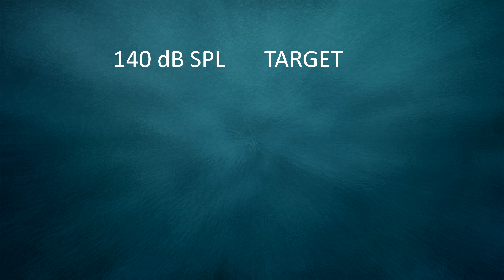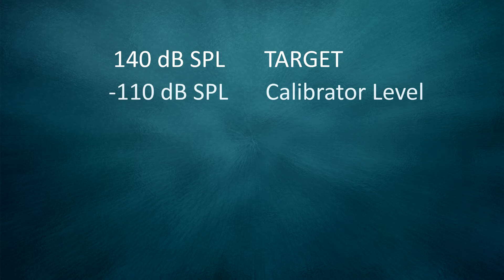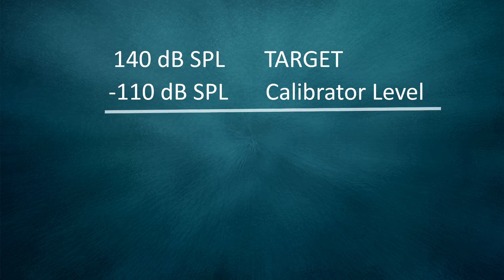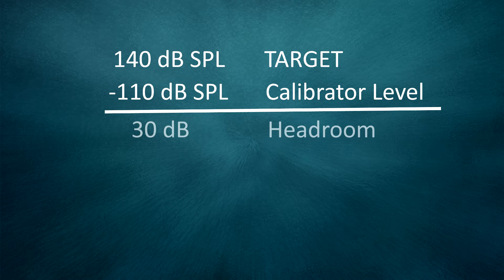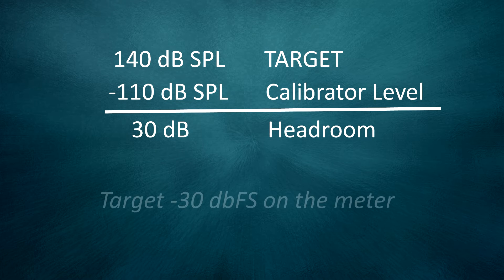Since my target for today's measurement session is 140 dB, and this calibrator is producing a level of 110 dB, I need to adjust my preamp to allow 30 dB of headroom over this 110 dB tone.